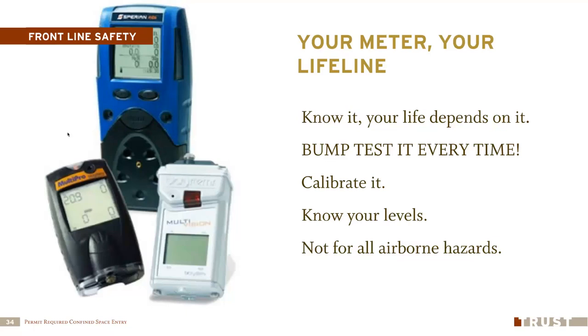If it doesn't, I need to recalibrate. Does that mean I need to send it back to the supplier or the manufacturer? The answer is no, you can do your own calibration. You need this cylinder of calibration gas, and you need your owner's manual to take you through it.